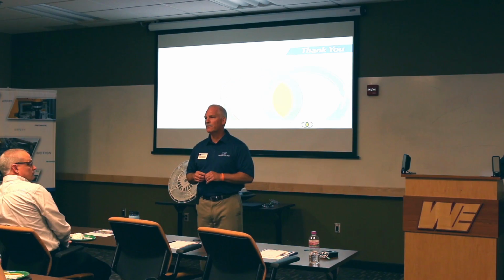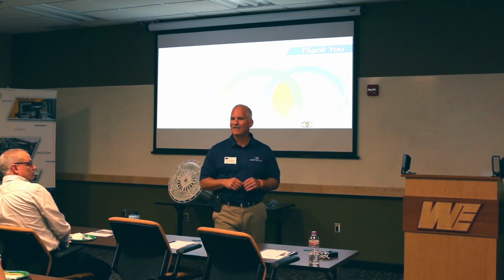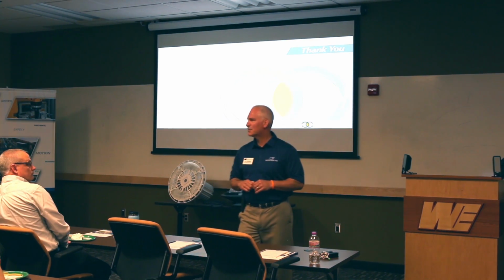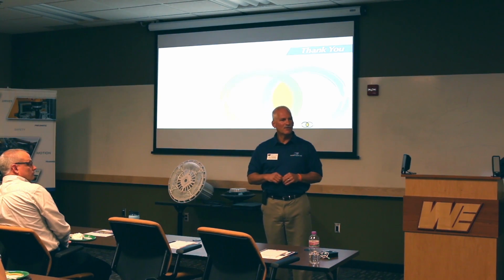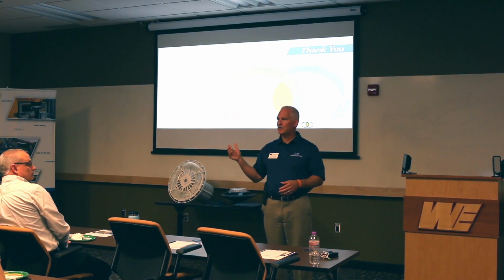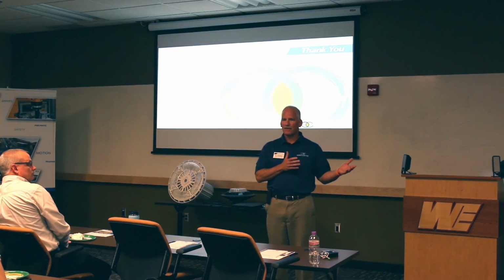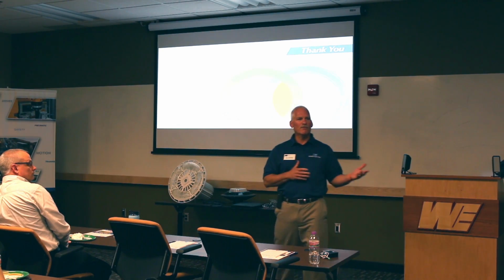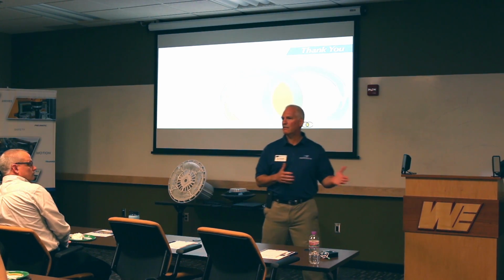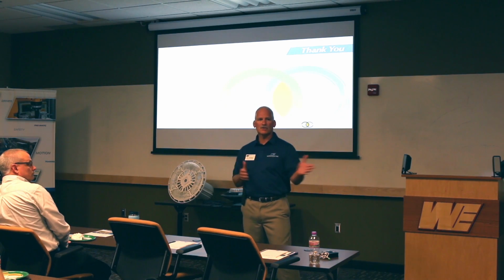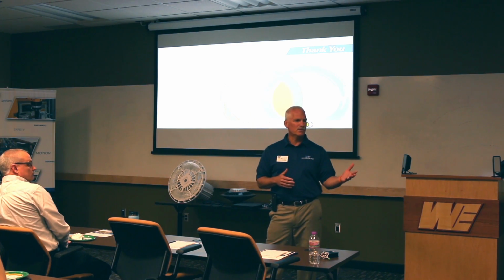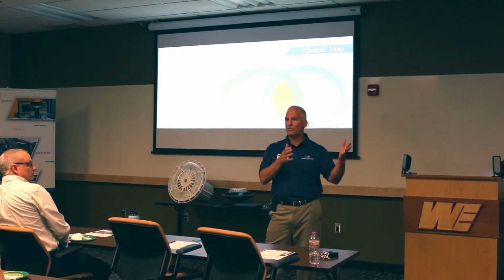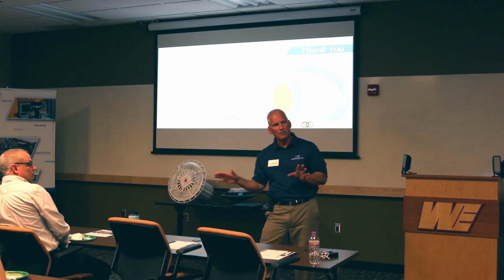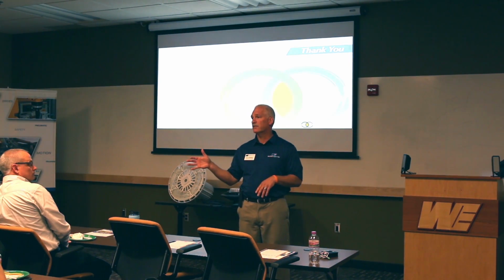Now's the time of year where people like Randy get called often because he's the drive guy. The drive failed because a lightning storm came through. Well, the lightning storm wasn't planned for up front because a lightning arrestor wasn't put in, transient voltage surge suppression wasn't put in, or some other equipment down the line may have failed because of that.